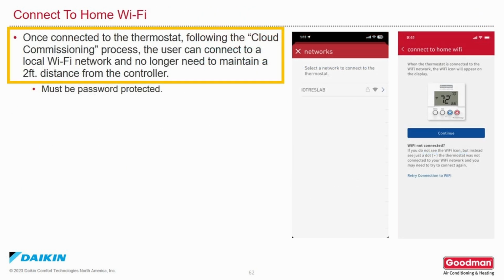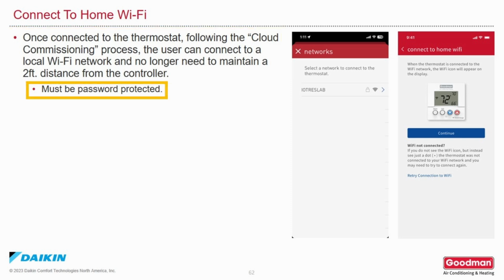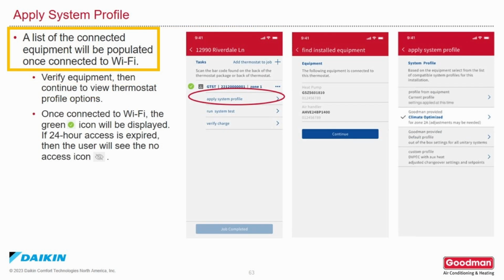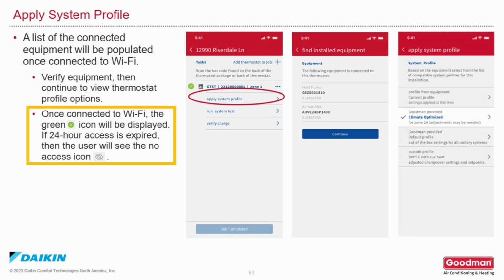Once you're connected to the thermostat, following the cloud commissioning process, you can connect to a local Wi-Fi network and no longer need to be within 2 feet of the controller. It must be password protected. It will show a list of equipment once you are connected to the Wi-Fi. Verify equipment, then continue to view the thermostat profile options. Once you're connected to the Wi-Fi, the green icon with the check mark in it will be displayed. If the 24-hour access is expired, then you will not see that icon.